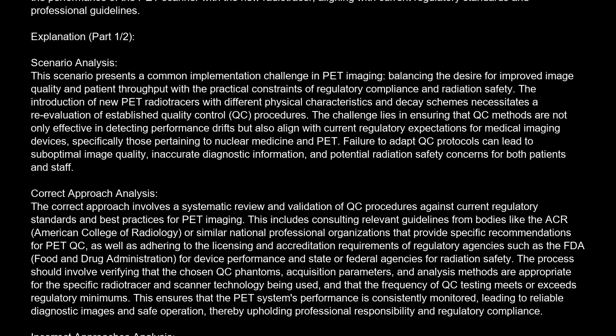The process should involve verifying that the chosen QC phantoms, acquisition parameters, and analysis methods are appropriate for the specific radiotracer and scanner technology being used, and that the frequency of QC testing meets or exceeds regulatory minimums. This ensures that the PET system's performance is consistently monitored, leading to reliable diagnostic images and safe operation, thereby upholding professional responsibility and regulatory compliance.